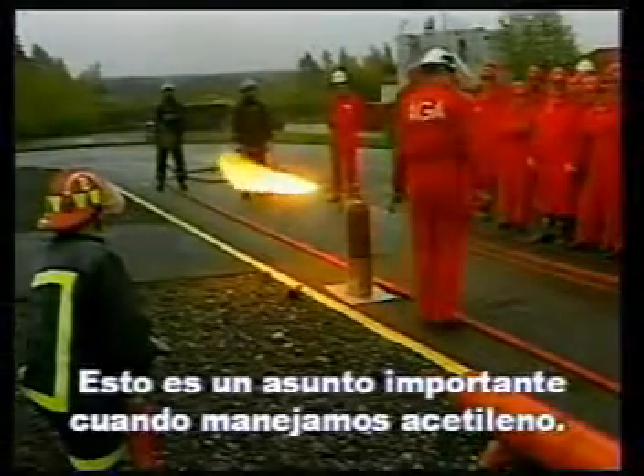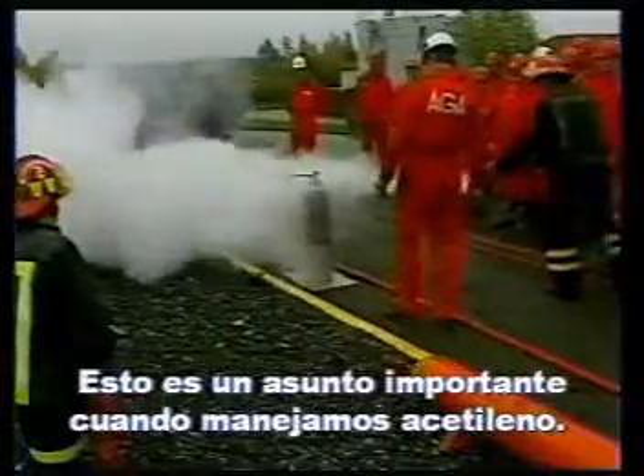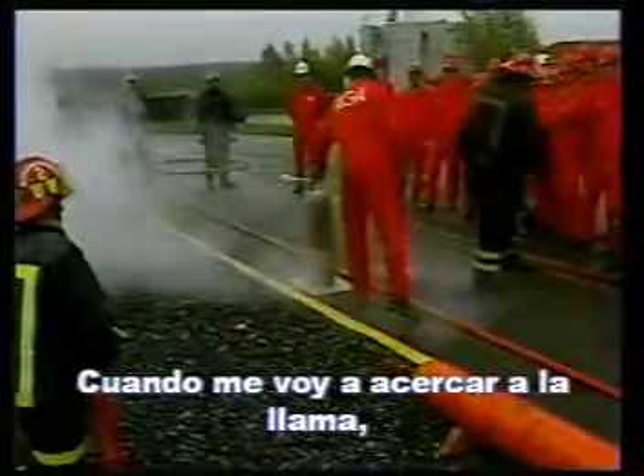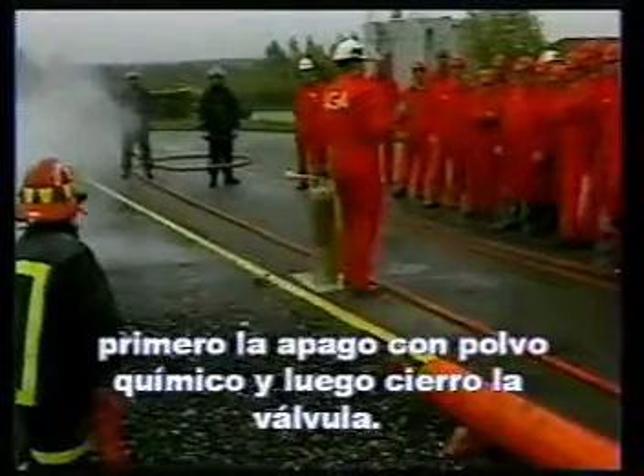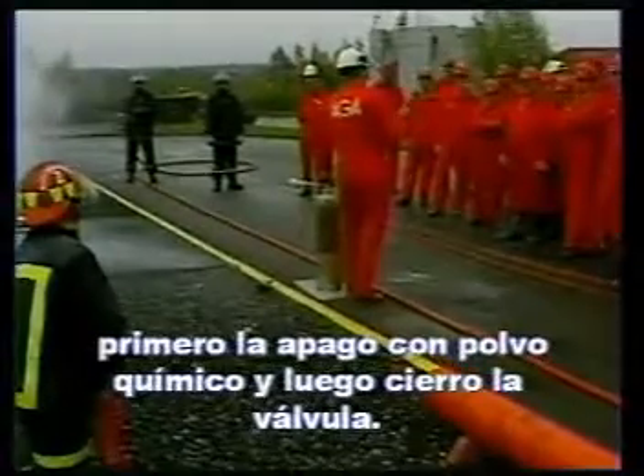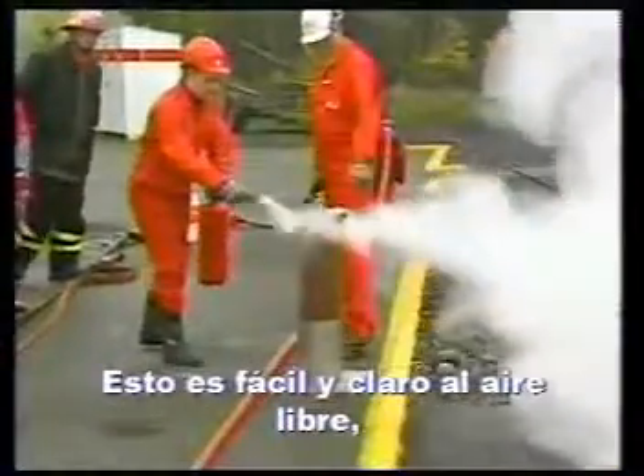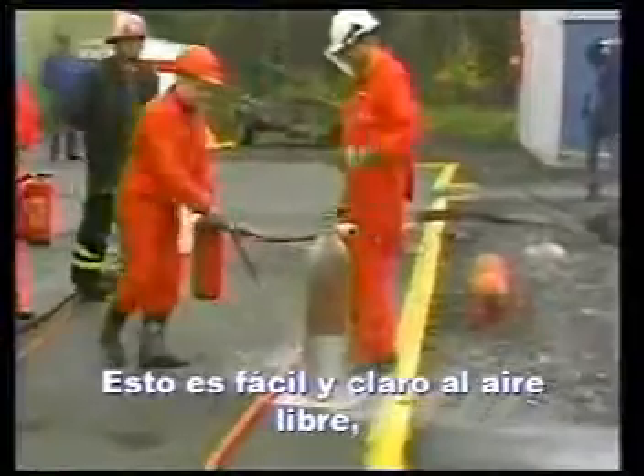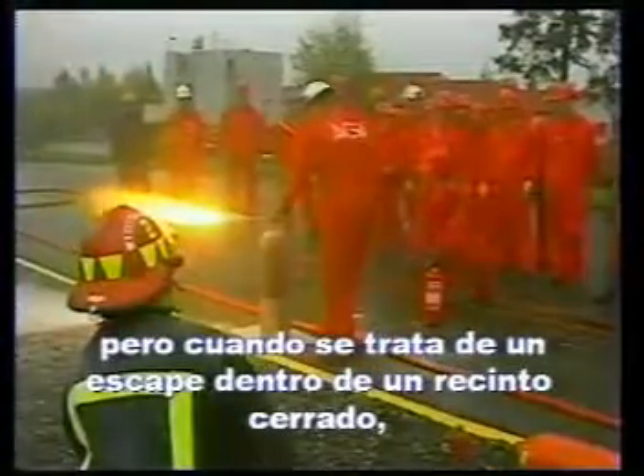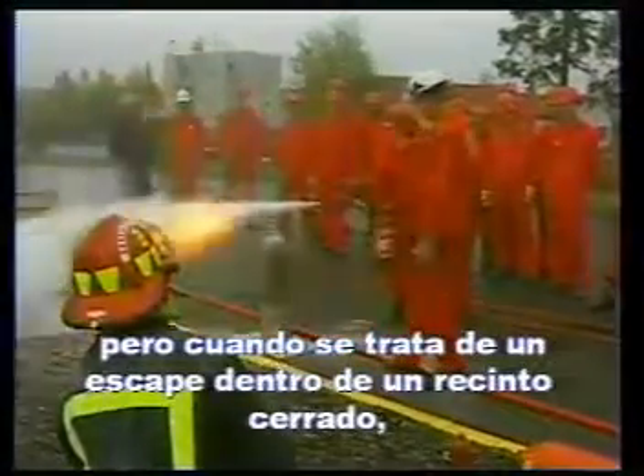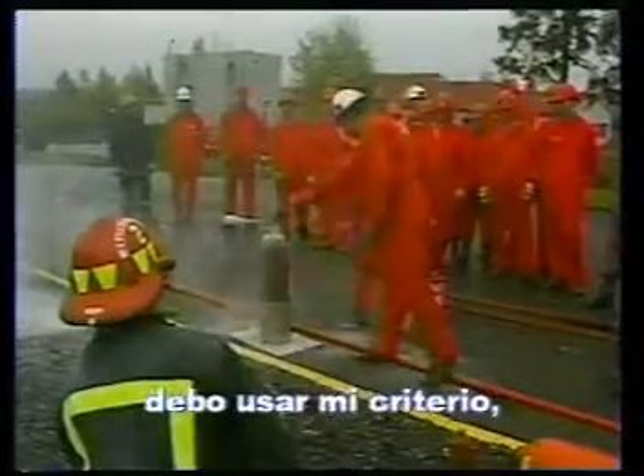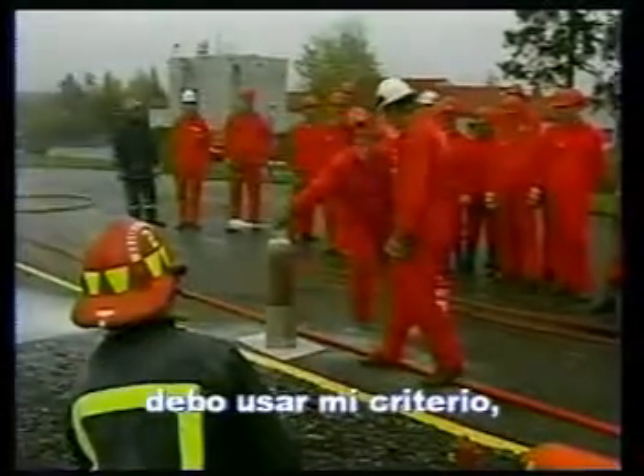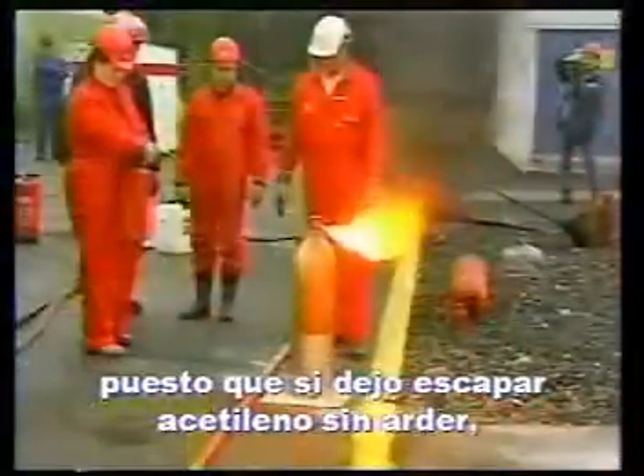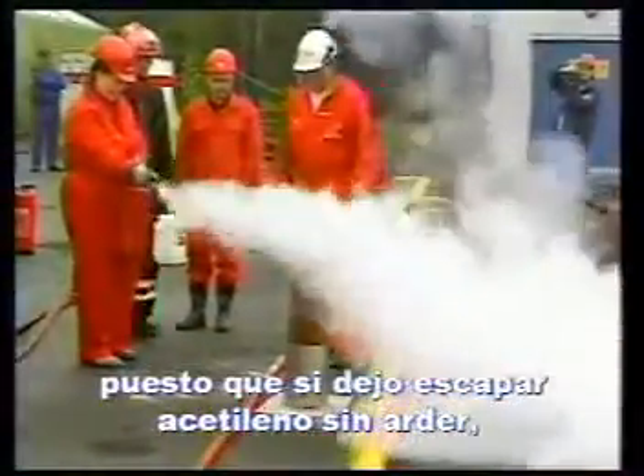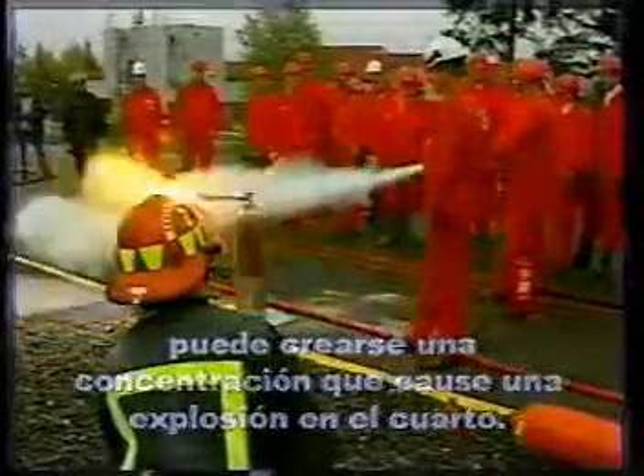Also here, we would like to shut off the gas supply, but the flame is very hot. And in order to get close to the valve to do that, we kill the flame with a powder extinguisher. And now, of course, we have to rush to close the valve. In open air, there's no problem, but indoors, there is more to it. You will have to use your judgment, because if you allow unignited gas to escape, you may cause a room explosion. Acetylene reignites very easily.